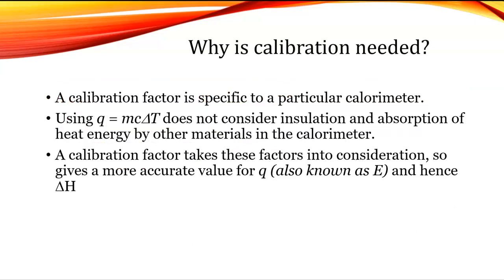As I said, calibration is needed so that we can relate specifically the Q to the change in temperature, because otherwise Q equals MC delta T is not taking into effect that we've got some insulation and there's going to be heat absorbed, but also that we're not losing heat to the surroundings. So it's a win and loss, but mostly we win. The calibration factor takes everything into account and is usually pretty consistent across all temperature changes in the calorimeter. We might use Q or we might use E for energy as we go ahead, so don't be confused. It's just me jumping around a bit with Q versus E.